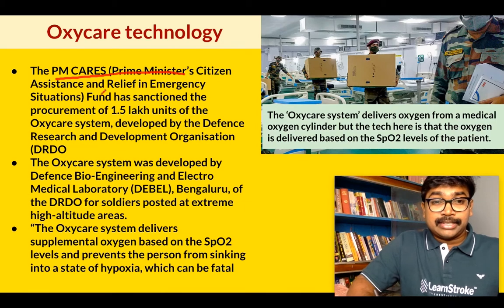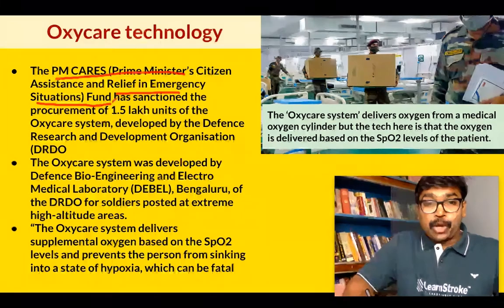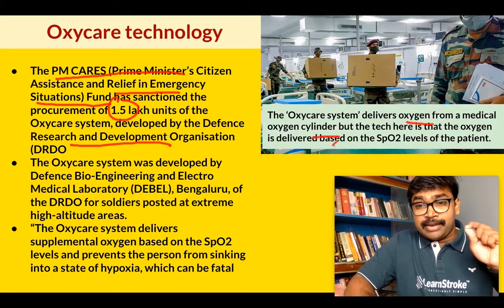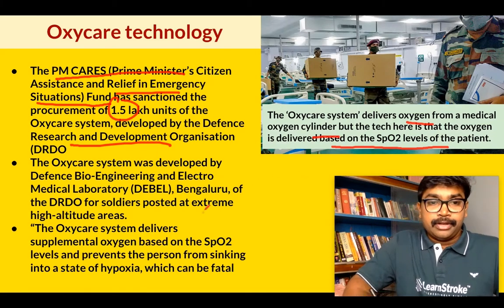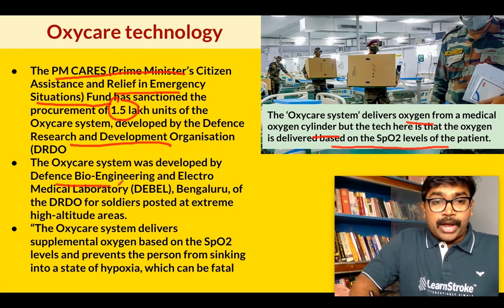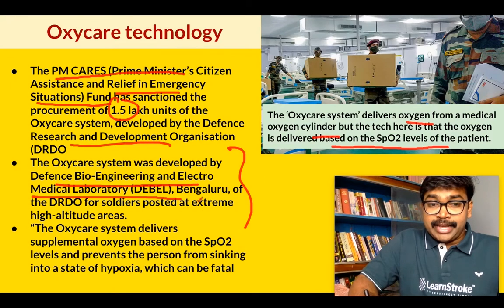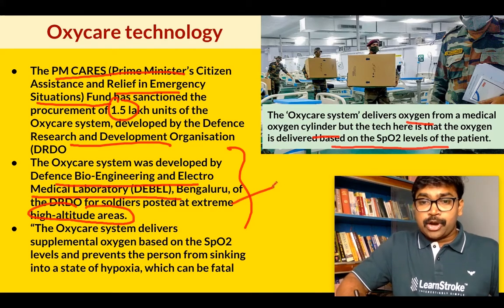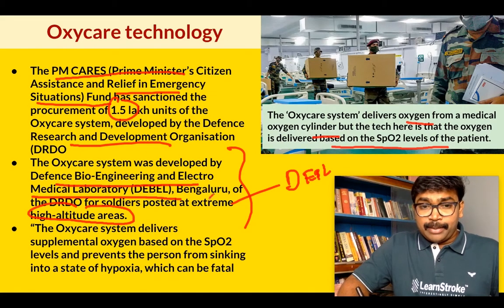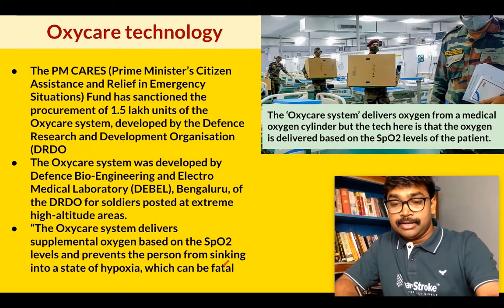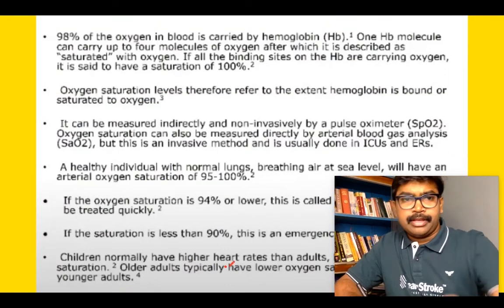PM CARES Fund — Prime Minister's Citizen Assistance and Relief in Emergency Situations Fund — has sanctioned procurement of 1.5 lakh units. DRDO is making them. The technology delivers oxygen from a medical cylinder based on the patient's SpO2 level. DEBEL stands for Defense Bioengineering and Electro Medical Laboratory of Bengaluru, which originally created this for army soldiers posted at extreme high altitudes.